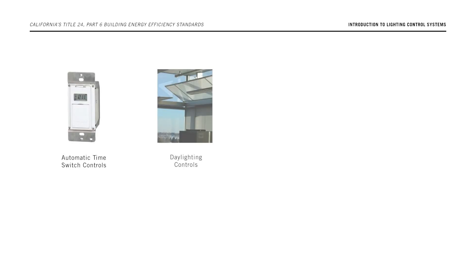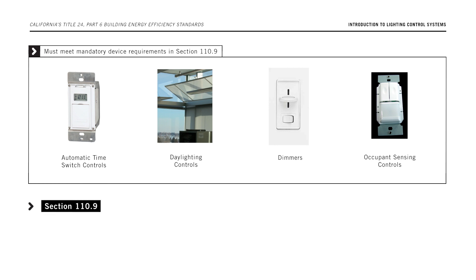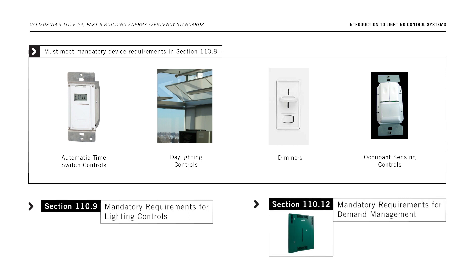Automatic time switch controls, daylighting controls, dimmers, and occupant sensing controls must meet mandatory device requirements in section 110.9 of the Energy Code. Demand response controls must meet the requirements in section 110.12 of the Energy Code.